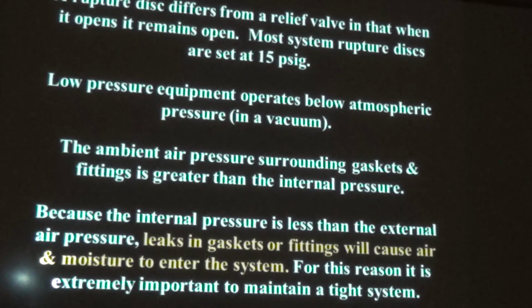A rupture disc differs from a relief valve in that it opens and it stays open. If you get a chance, go into YouTube and look up rupture disc, and you can watch them blow up. They're pretty cool. Most system rupture discs for air conditioning blow at 15 pounds PSIG. And if you think about it just for a minute, that actually means they blow at about 30 pounds. 15 PSIG at 14.7 is really closer to 30 pounds.